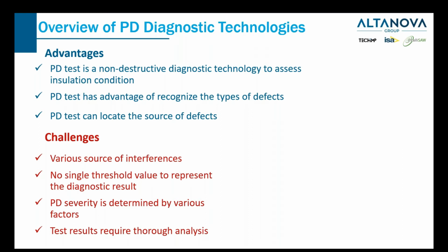What's the reason that people select PD testing instead of the other testing technologies? I mean, even if we're talking about cables or switchgears, there are tons of diagnostic testing technologies available. What's the uniqueness of partial discharge testing? So here are the three major advantages of using PD testing. First, PD testing is a non-destructive testing technology.